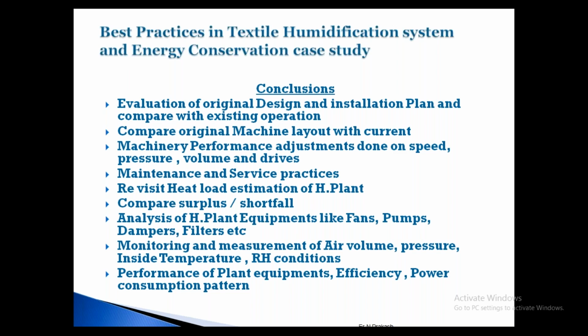Then revisit the heat load estimation, the total heat load of the humidification plant. Twenty years back they designed the plant based on some dry bulb and wet bulb values. So we also have to collect information from the meteorological department. Previously they declared 43 for Pune, or for this place. Now it may be 46. They recalculate and publish meteorological data as an average dry bulb temperature of 45 or 46. Based on that, if you calculate CMH, we require more air quantity, more water, and so on. So we have to do the heat load estimation, compare, and see whether there is a surplus or a shortfall.